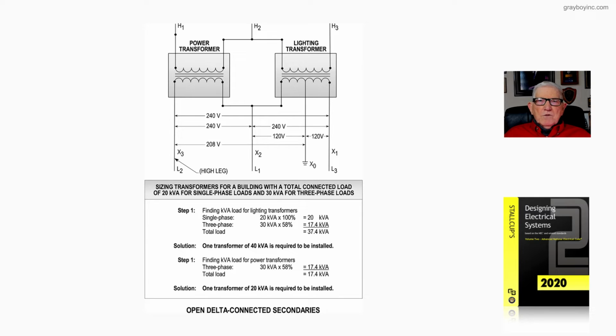So if you took 1 and divided it by 1.732, the square root of 3, you come up with your 58% rule. Now let's apply the calculation procedure for sizing these transformers. Step 1, single phase, 100%. So you take 100% of the single phase load, 20 kVA. Then you would take that 58% of the three phase load, which is 17.4, add them together, you come up with 37.4. Now again, remember the 58% is derived from 1 divided by 1.732, the square root of 3.